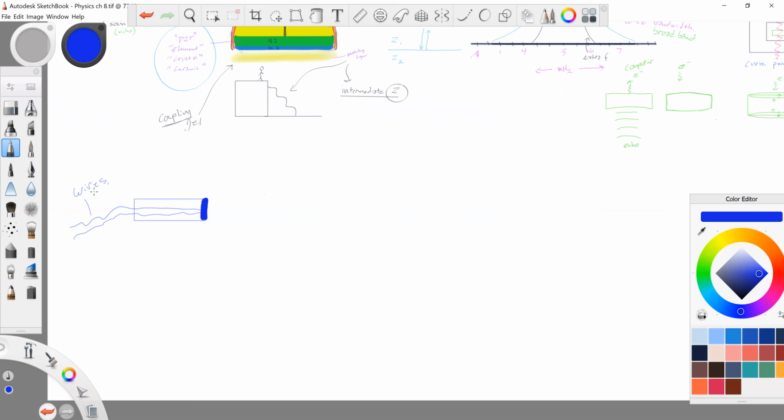So what they're saying is that whatever electrical frequency is put into the element is what the frequency is. So if you're exciting the electrical wire at 5 megahertz, you will have a 5 megahertz wave produced. If it's 10 megahertz, a 10 megahertz wave is produced. So that is true. You are able to change the frequency by changing the frequency in the wires itself.